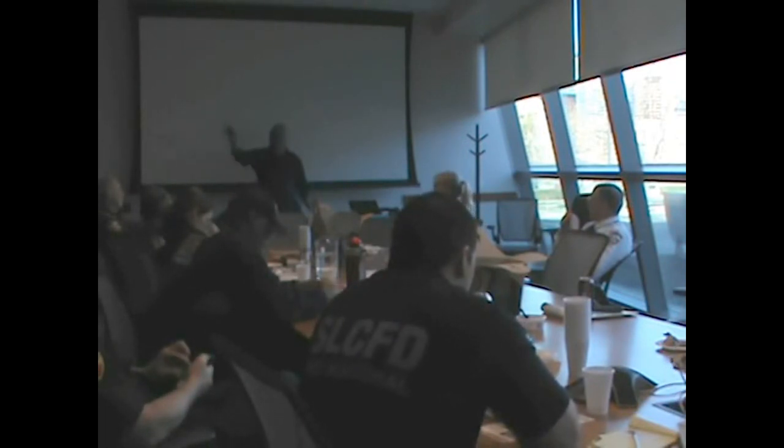So with a change of occupancy, now you have to look at the fire escape system again. This ladder is no longer sufficient. This ladder used to do for 10 people, and you've got 100 people here now, or it turns residential or whatever. You say, I want a stair, now it must conclude in a staircase. Oh, we have no room, we're over a sidewalk. Yeah, cantilever stairs. You're going to have to put it up 12 to 14 feet in the air, and it's going to be a balanced staircase that comes down to the ground. And it's going to get fatter. It's going to come out 6 to 7 feet wide.